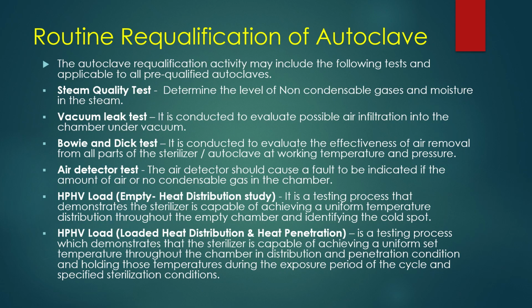The first test is steam quality test. It determines the level of non-condensable gases and moisture in the steam. The second one is vacuum leak test. It is conducted to evaluate possible air infiltration into chamber under vacuum. Third one is Bowie-Dick test. It is conducted to evaluate the effectiveness of air removal from all parts of sterilizer at working temperature and pressure. Fourth one is air detector test. The air detector should cause a fault to be indicated if the amount of air or non-condensable gas in the chamber exceeds the limit.